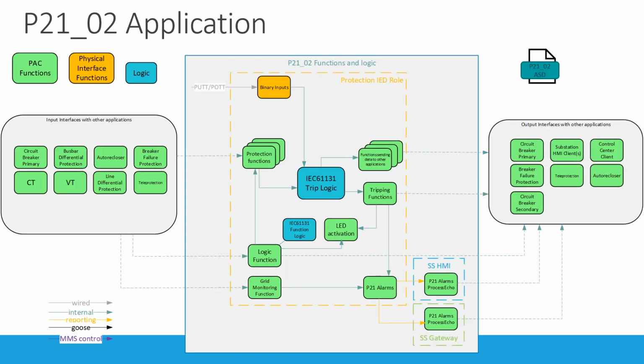You can do the same exercise for the distance protection. It's a completely different type of application. It also has a binary input, in our case just an example to switch between the overreach and underreach setting. There are some protection functions, and a trip logic which we modeled in 61131, documenting how trips are created from the operations of the different distance protection zones.